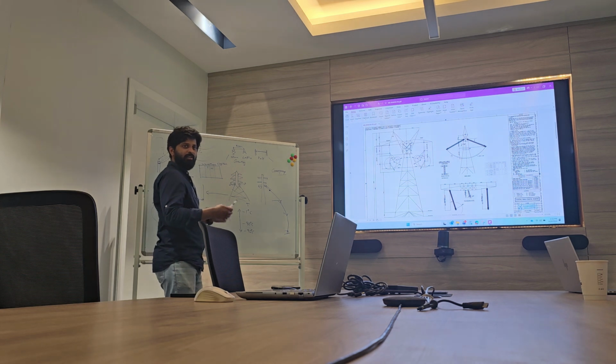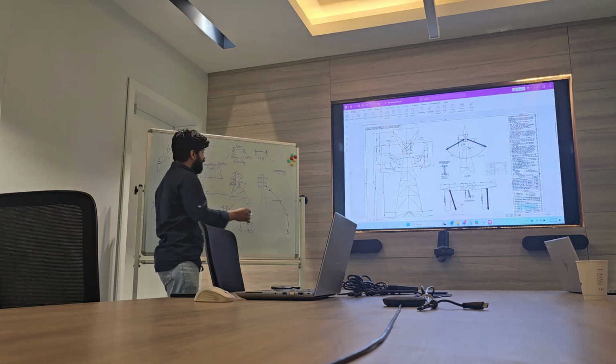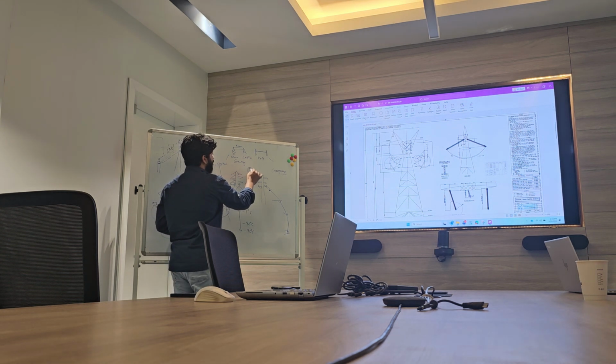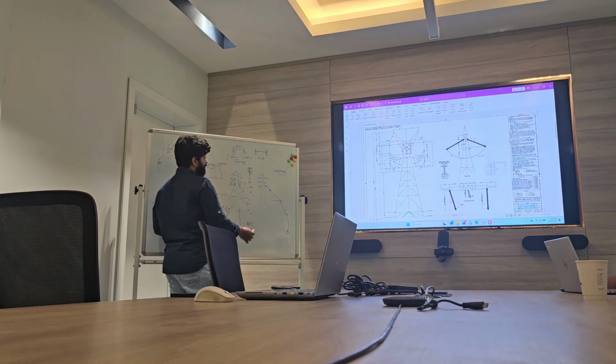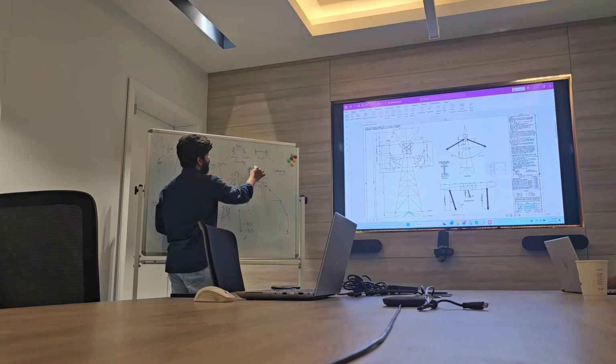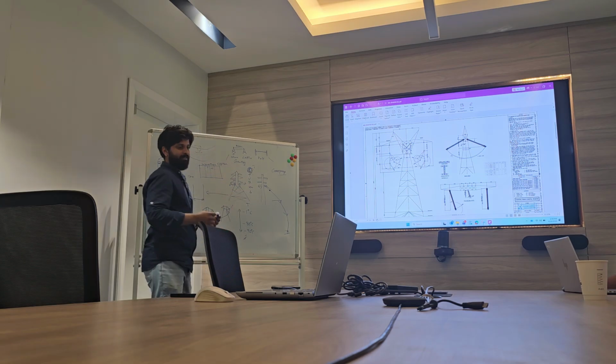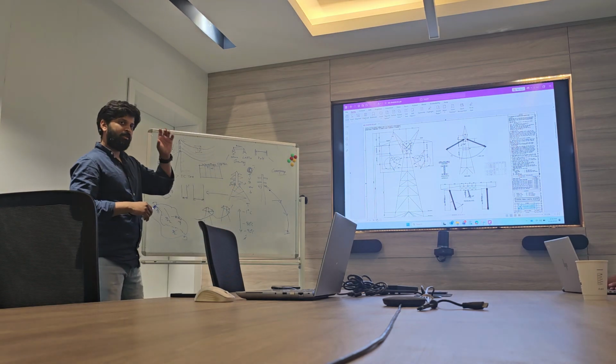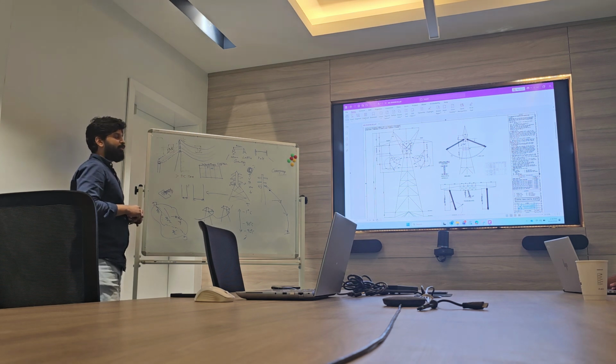So when you have too much current flowing through the conductor, you decide the conductor size required based on voltage level, current level, power to be transferred, and distance for the power to be transferred. Yes. Weather also, and temperature. How much it can take. Okay. Based on that, your cross section area for the OPGW is decided.